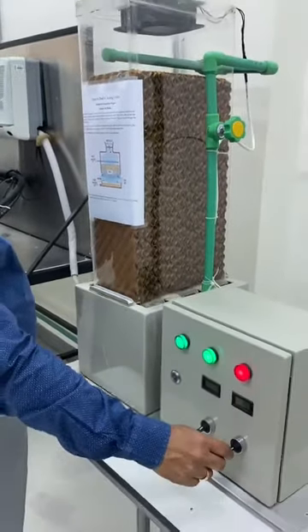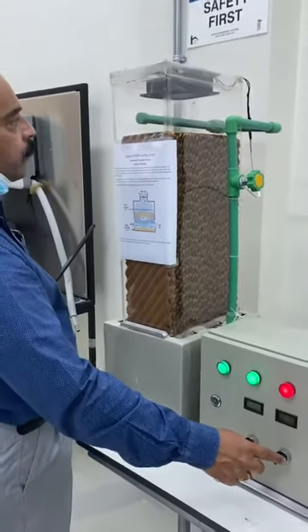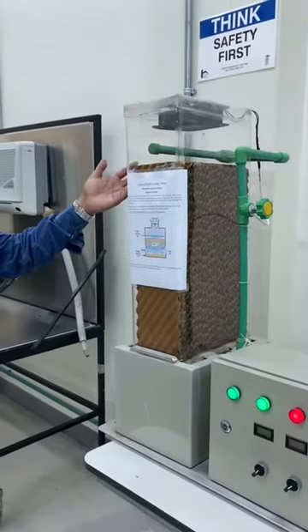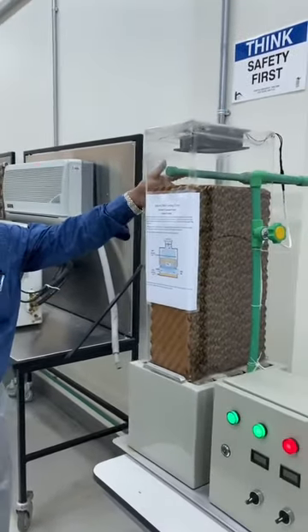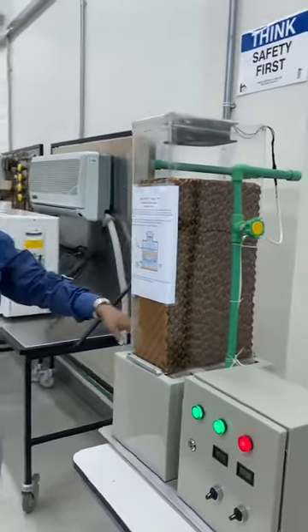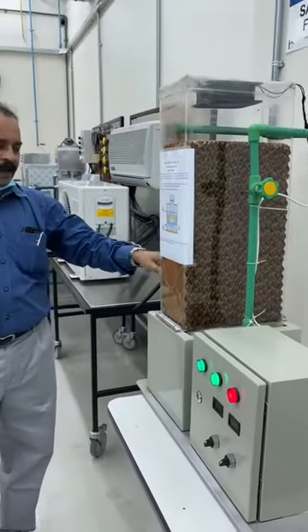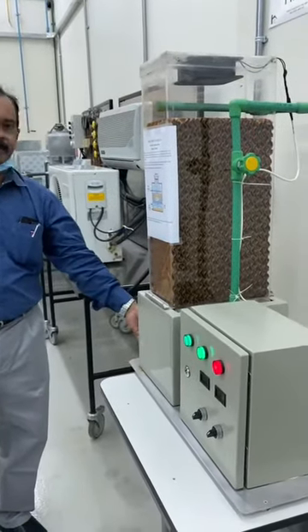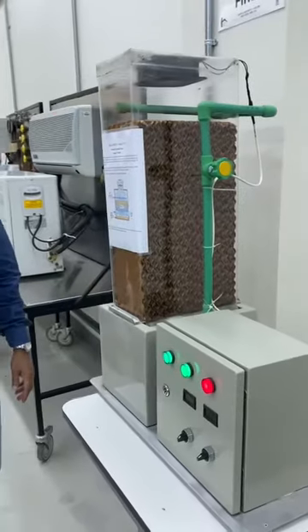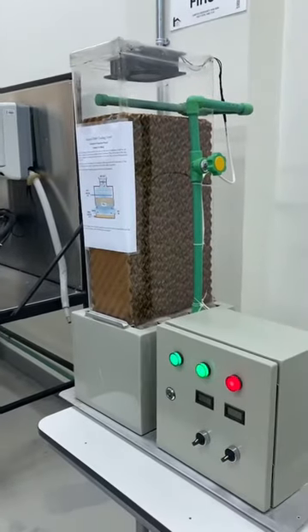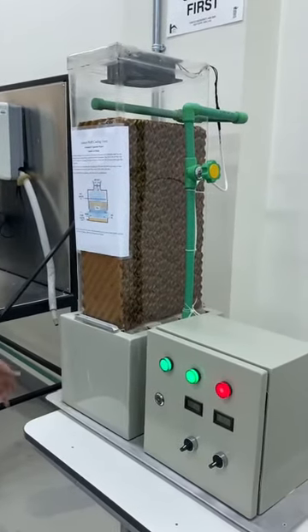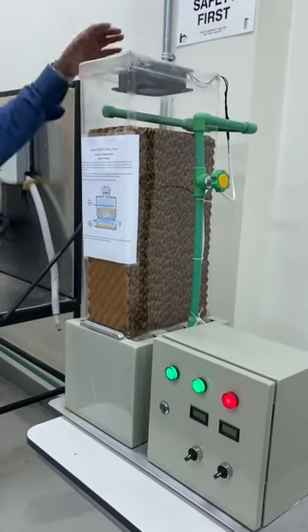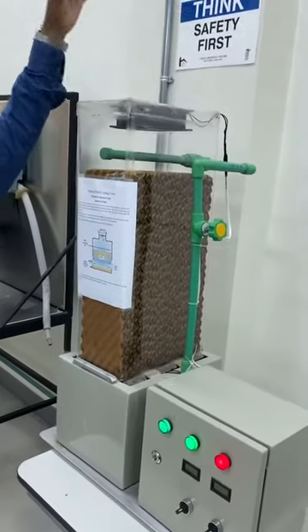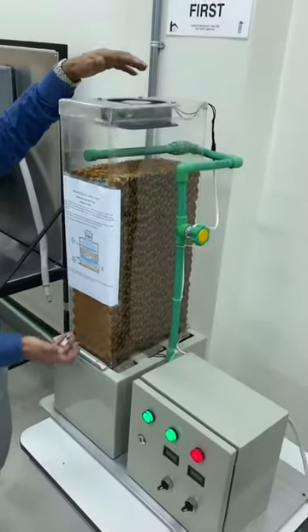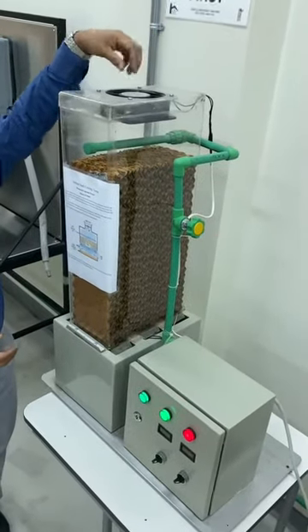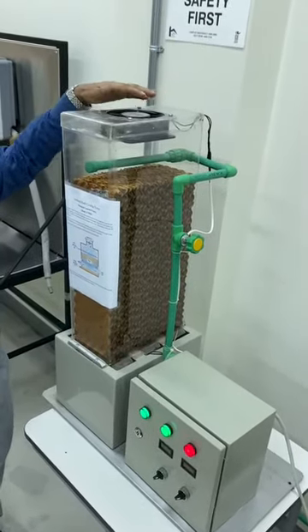But unfortunately, there is no water. Otherwise, we could have seen the water sprayed through the nozzles and collected here, and that can be used for condensing the refrigerant vapor in the condenser and becoming liquid refrigerant. And here you can see this air is going out after going through the fills and up. This is the place where the air is going, same like the previous one also.